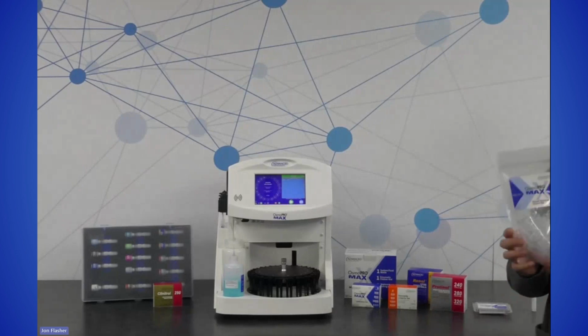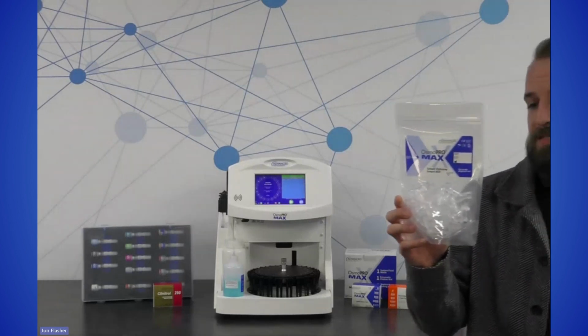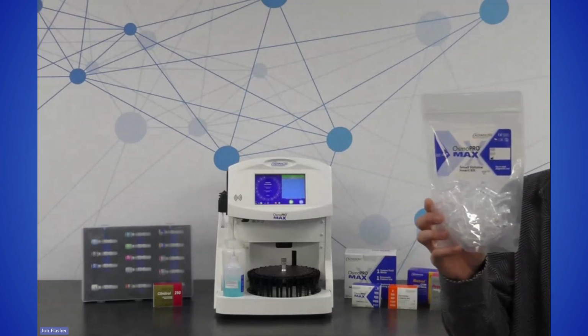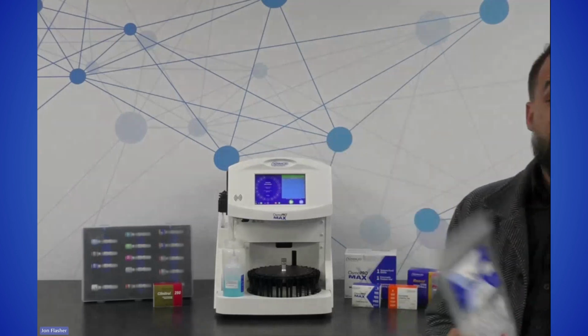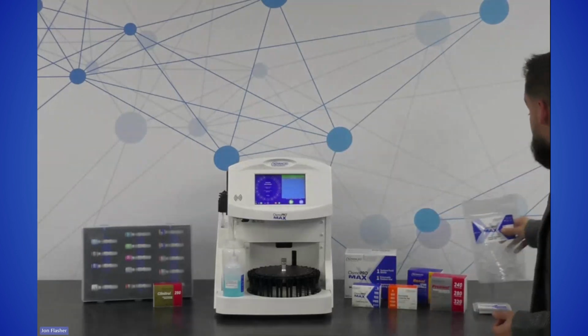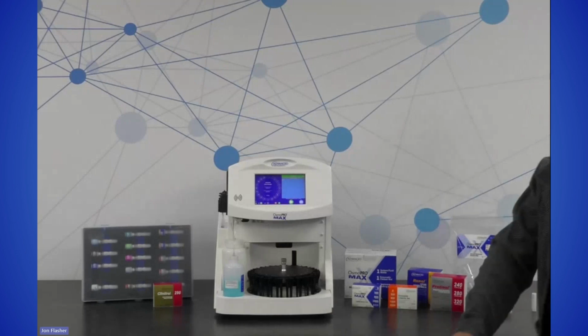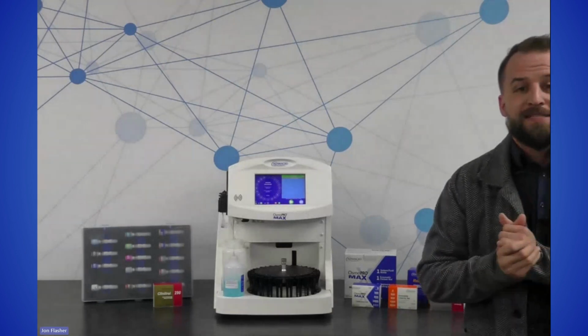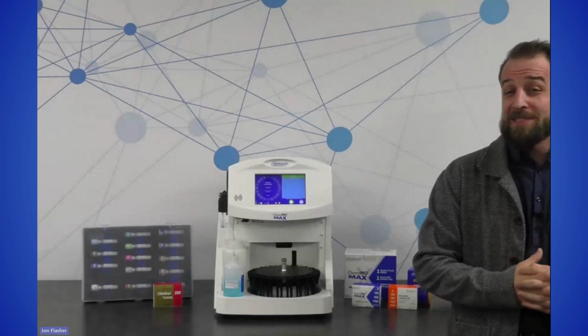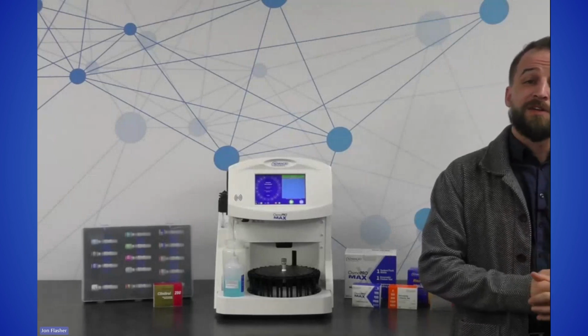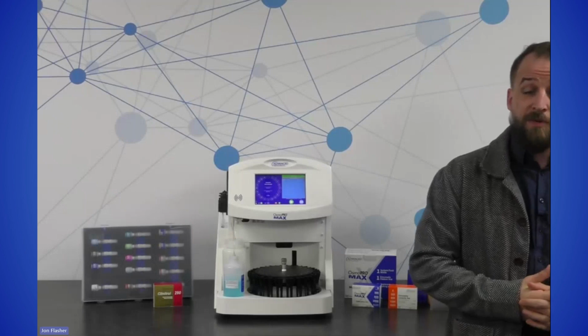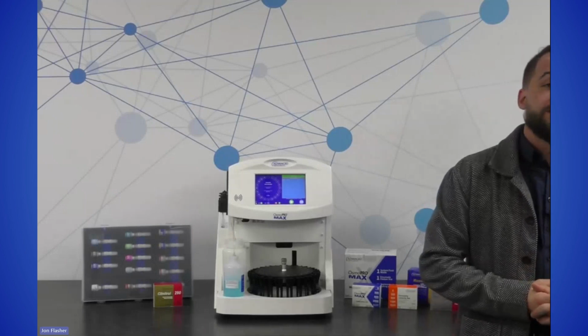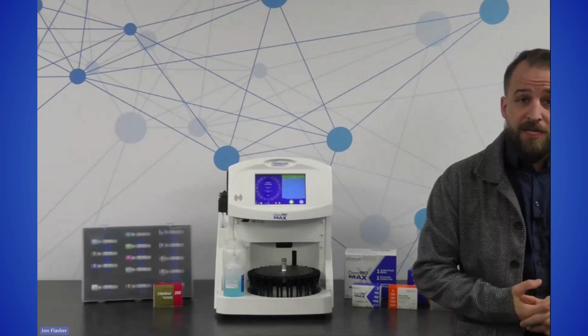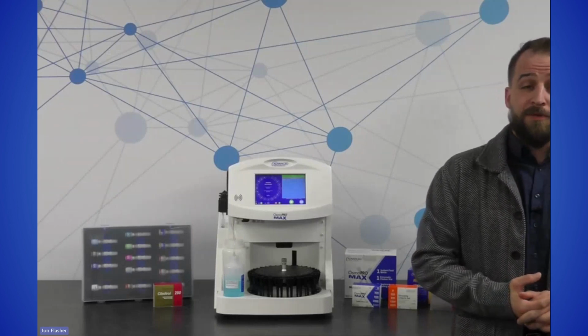Something else that it comes with are these small sample volume inserts. What these do is, if you have a short sample, maybe because it's just a tough stick, or you're sharing it among other testing in the laboratory, or maybe a pediatric sample, the instrument does accommodate testing down to 190 microliters. So you can simply transfer your serum or plasma or urine into one of these small volume inserts and run a 190 microliter sample.